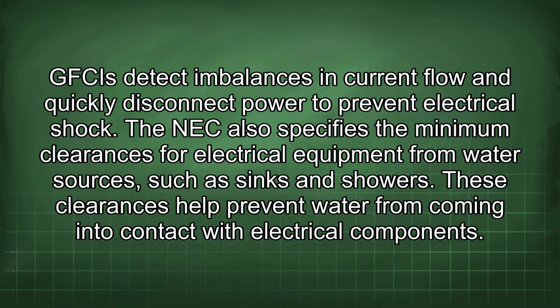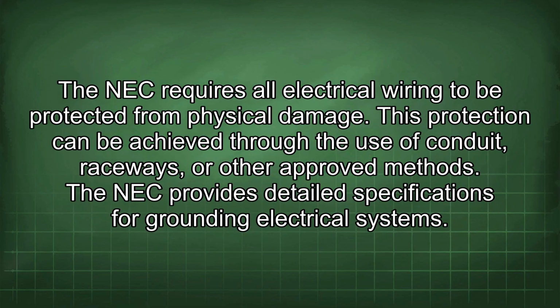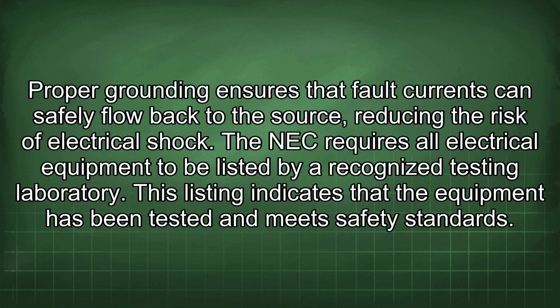The NEC also specifies the minimum clearances for electrical equipment from water sources, such as sinks and showers. These clearances help prevent water from coming into contact with electrical components. The NEC requires all electrical wiring to be protected from physical damage. This protection can be achieved through the use of conduit raceways or other approved methods. The NEC provides detailed specifications for grounding electrical systems. Proper grounding ensures that fault currents can safely flow back to the source, reducing the risk of electrical shock.